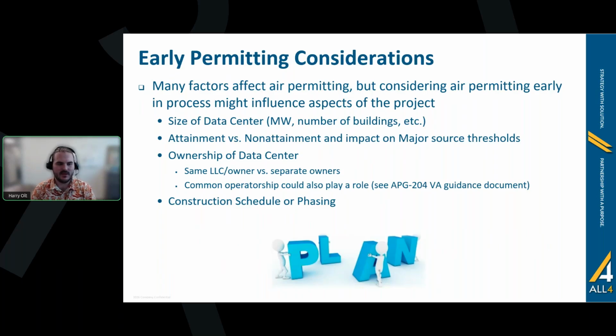Additionally, the ownership of the data center or campus should be considered when evaluating air permitting. If all of the campus buildings have common ownership, or if a new facility is being constructed adjacent to another facility under the same ownership, agencies will usually aggregate those sources for purposes of comparison to the major source thresholds. However, if buildings have different majority owners, then the state air permitting agency might allow them to be considered separate sources, each with their own major source threshold, rather than being aggregated as one source. Common operatorship, even with differing common ownership, may also lend buildings to being aggregated by the state, and the Virginia guidance document APG 204 provides great information on this.